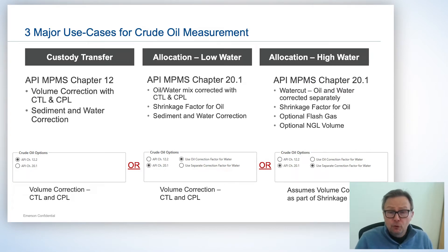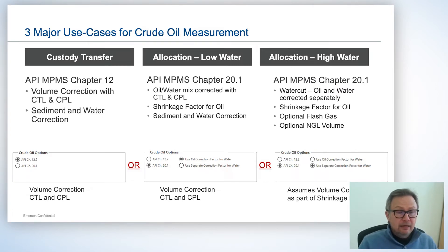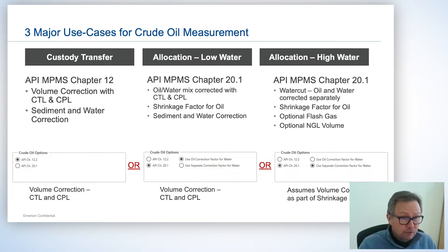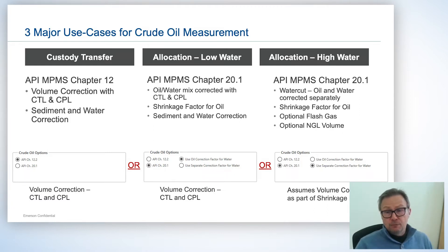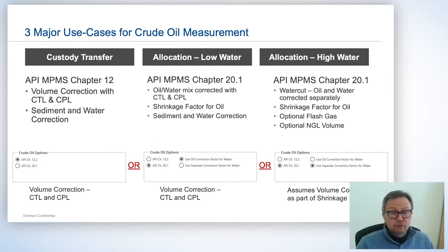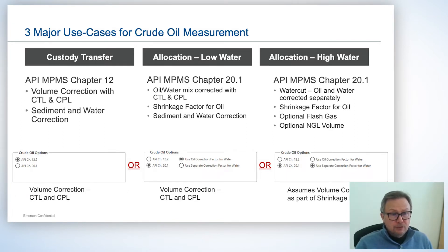We have three crude oil calculation types. The left-hand side is the type you're probably most familiar with: custody transfer. In custody transfer we use volume correction factors CTL and CPL, as per API Chapter 11.1, to correct for the effects of pressure and temperature on the oil. There's also an optional sediment and water correction. That's pretty much the standard crude oil custody transfer calculation that most people are familiar with.